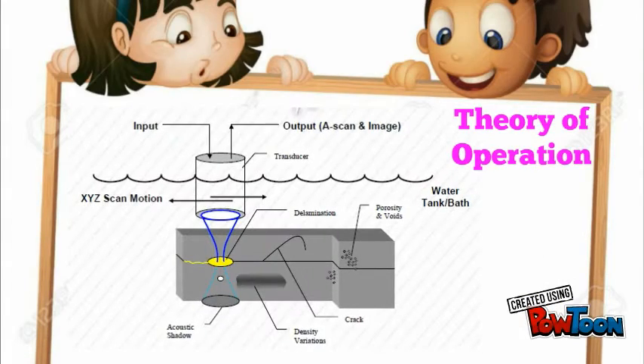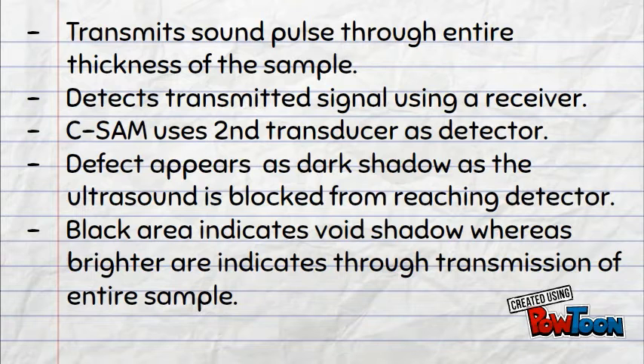Using the transmission method, sound pulses are transmitted through the entire thickness of the sample, causing voids to appear as dark shadows as the ultrasound is blocked from reaching the detector, as shown in the figure.